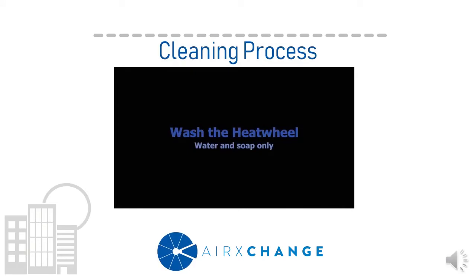So the second way to clean a segment, and in my opinion the most thorough way to clean it, is to use a soapy solution. I want to stress that using the vacuum method will remove the dust, but what it won't do is unclog the desiccant pores that are responsible for the vapor transfer function of the device, some of which may not be visible to the eye. By soaking the segments in a watery soapy solution, you're allowing the degreasing agent to thoroughly clean not only the face of the wheel, but all the way through the media as well.